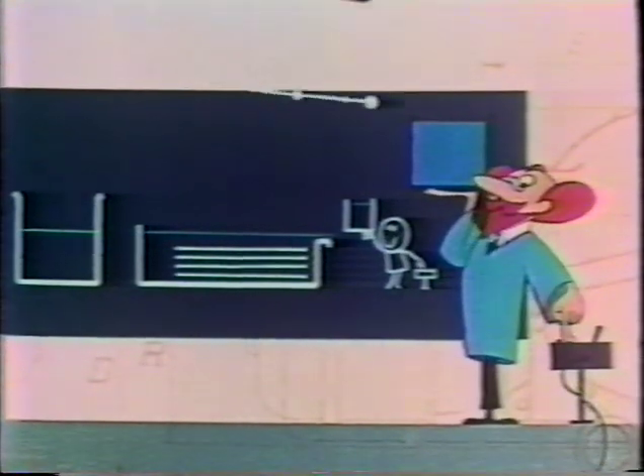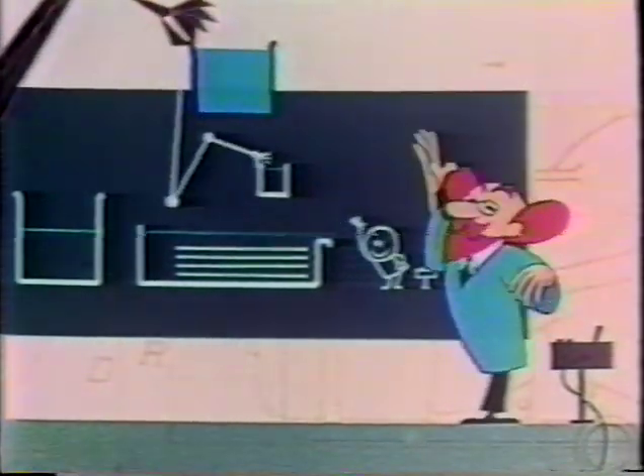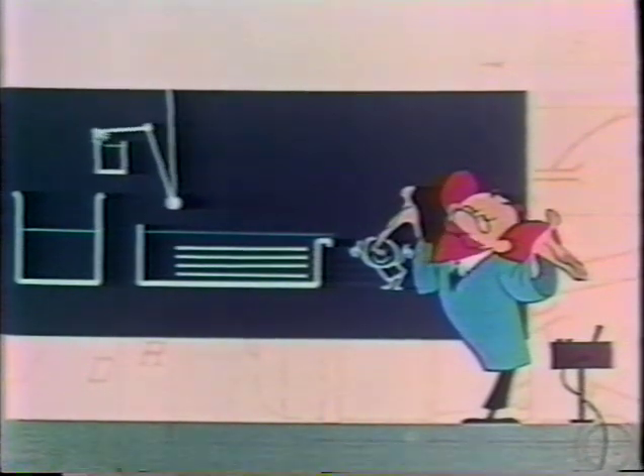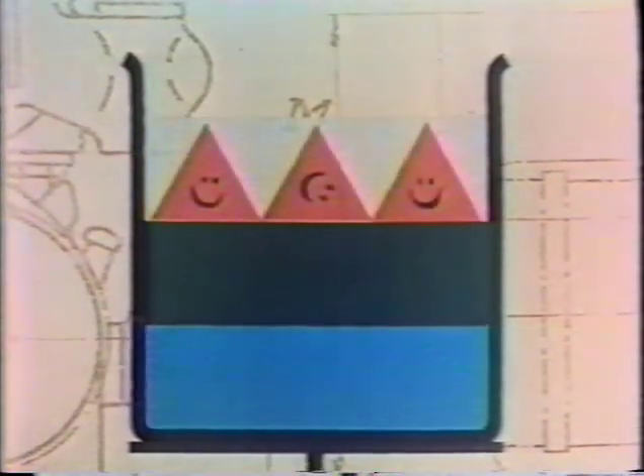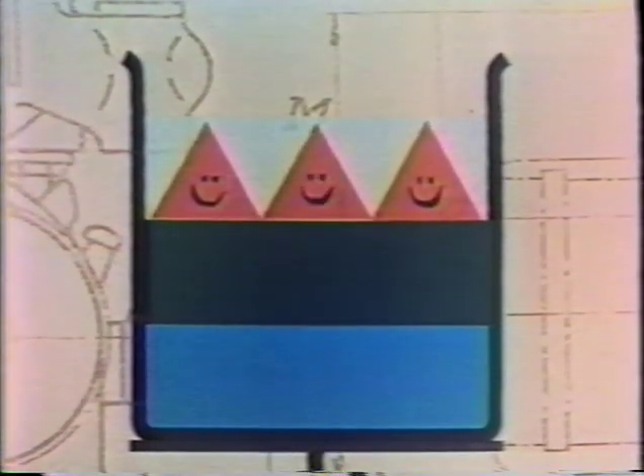It's possible to go even further in the application of gravity. Let's take the common case of trying to separate two immiscible liquids — oil and water, for instance. If the mixture is left in a simple batch settling tank, we shall soon find we have three layers. On the top, a clear layer, which we call the light phase. In between, a narrow layer of still unseparated feed material, which is known as the neutral zone. And on the bottom, the heavy phase.